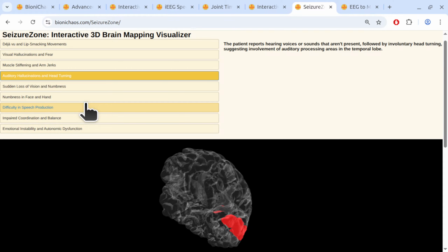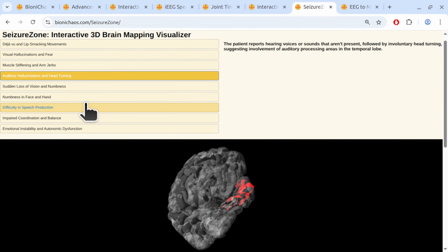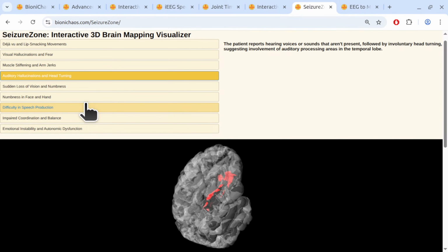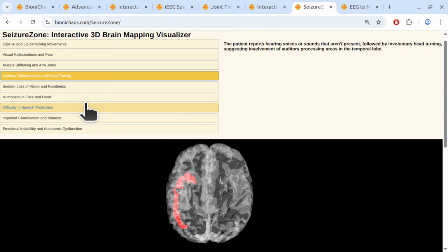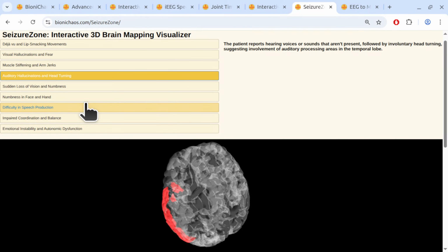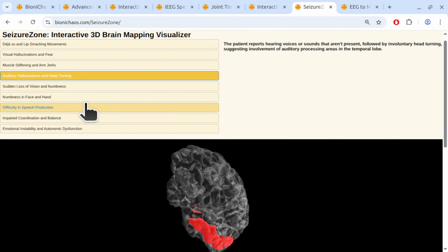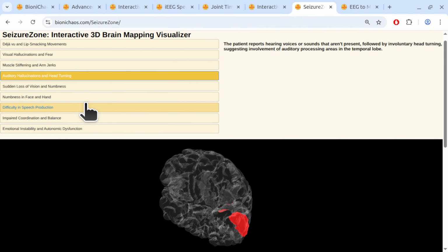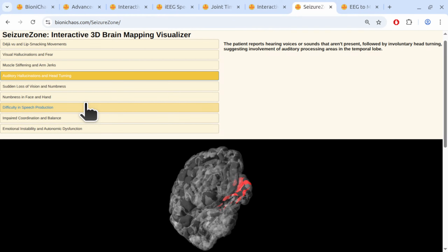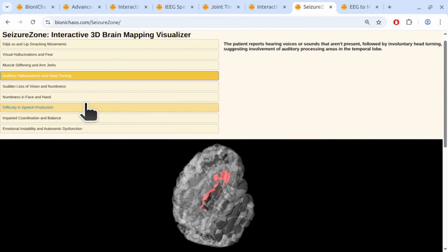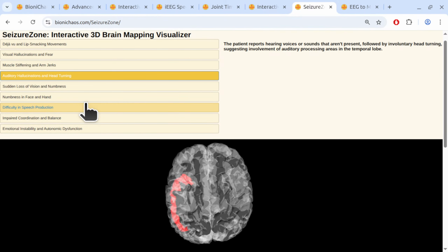It comes down to really stringent technical standards and critically careful expert human interpretation. A proper clinical EEG isn't just slapping on electrodes. It involves meticulous protocols, precise placement, usually using a standard system like the 10-20 International System to ensure everyone's recording from the same relative spots. Consistency. Exactly. And maintaining very low electrode impedance, that's the connection quality between the electrode and the scalp. You need a clean signal, minimal external noise, plus specific sampling rates to capture the brainwave details properly.